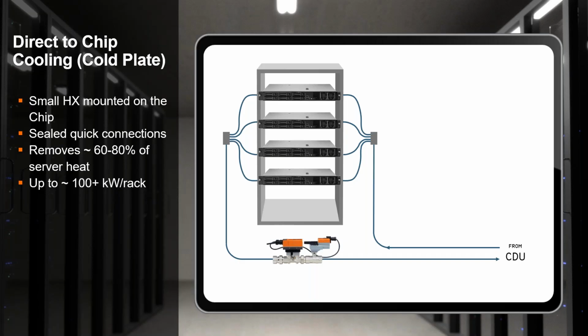And then in general, we're going to have a control valve on the return side. That control valve typically isn't modulating. What we're doing with that control valve is making sure that we have the absolute right flow for those 4 servers. Why would we not modulate that? Obviously, these computers are going to ramp up and ramp down and create different amounts of heat depending on what's going on. The answer lies in how quickly we get changes in computing power. We couldn't adjust the flow nearly fast enough to keep up with the instantaneous demand of changes in those servers.